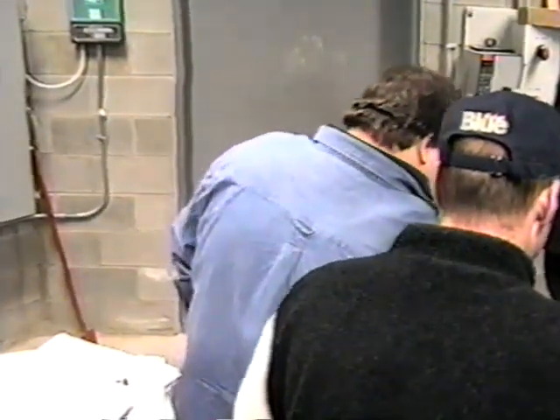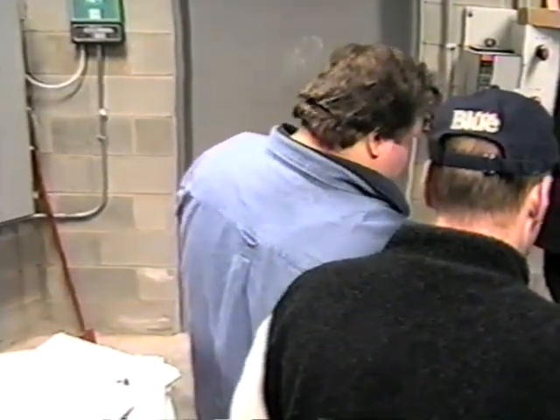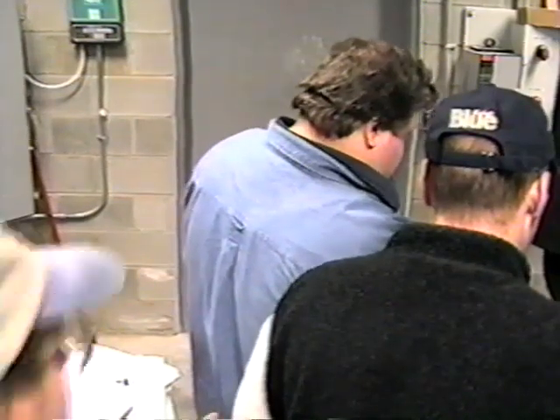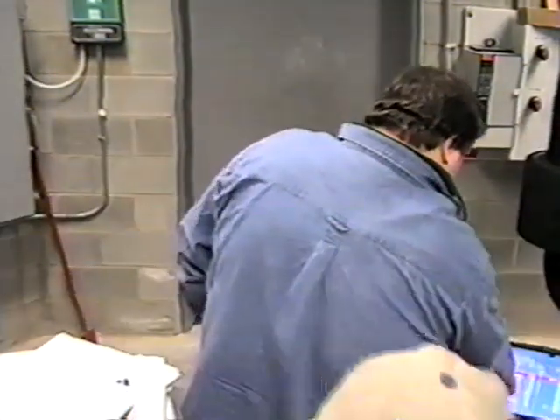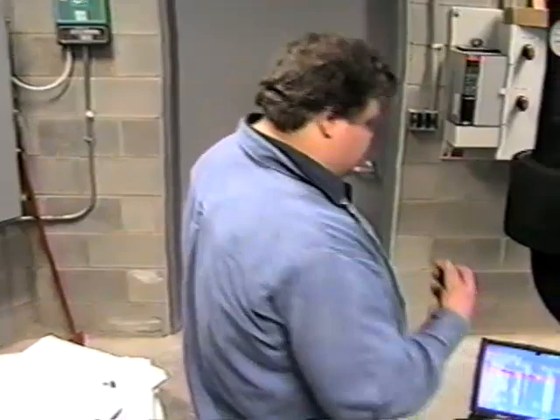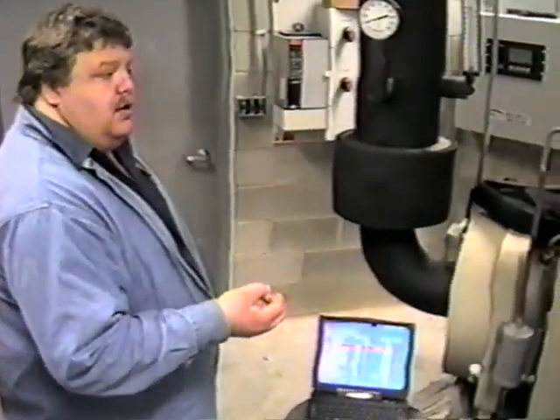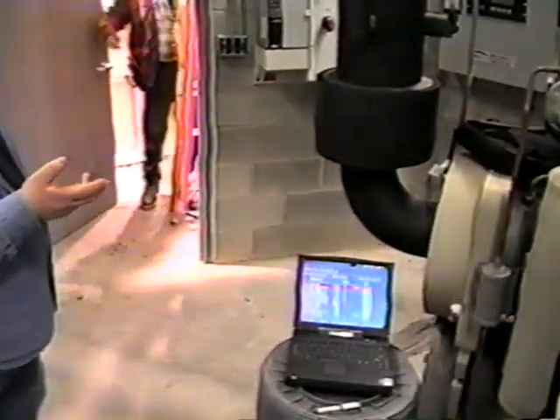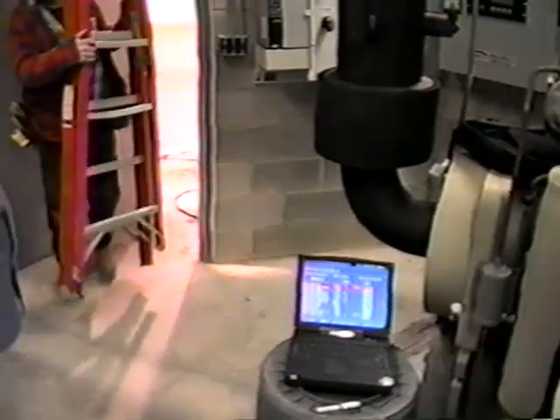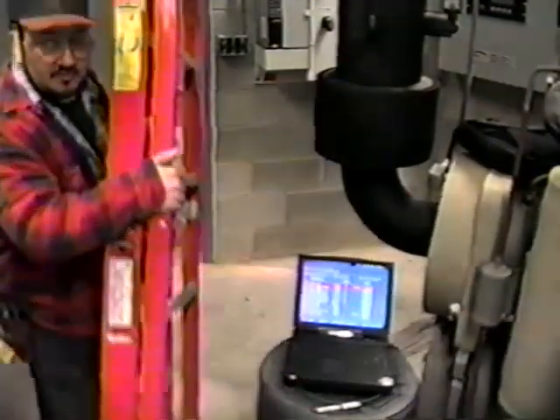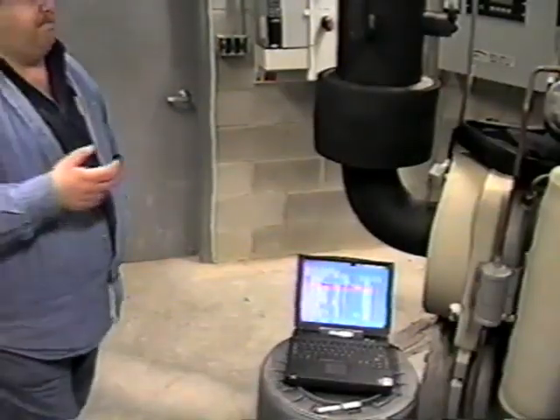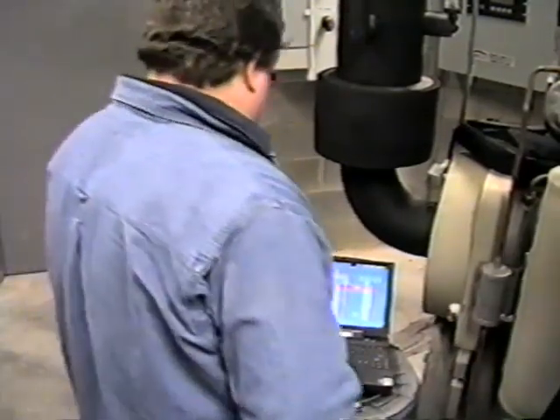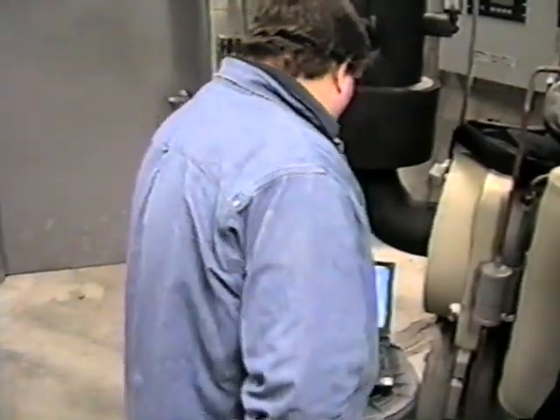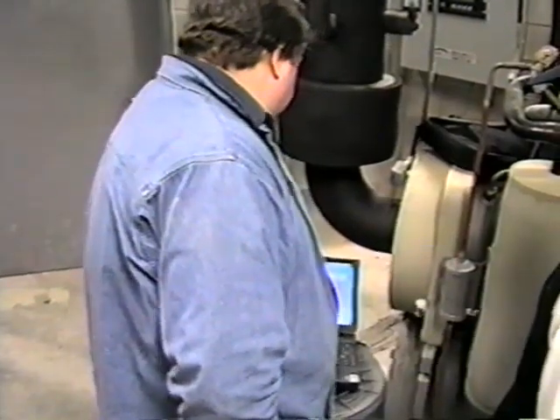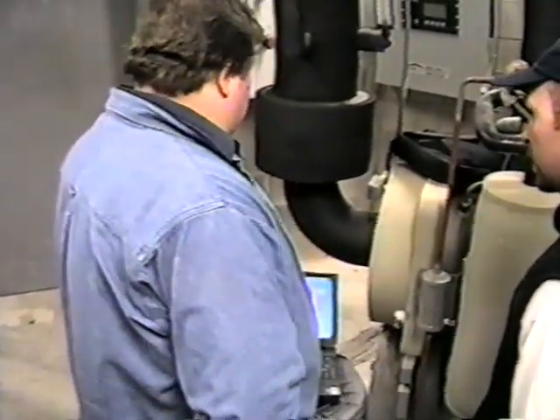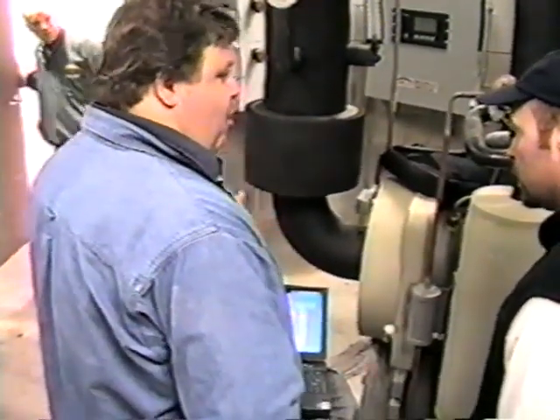Like right now, ice, it's giving you what your actual surface ice temperature would be. Chilled water pump status: chilled water pump 1 is your high-low speed pump, or your smart drive pump. And so this is going to tell you what it should be. Right now I've got the temperature set for 25, so we're not calling for cooling.